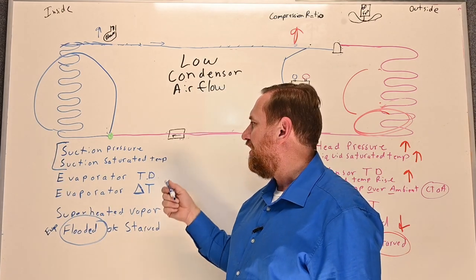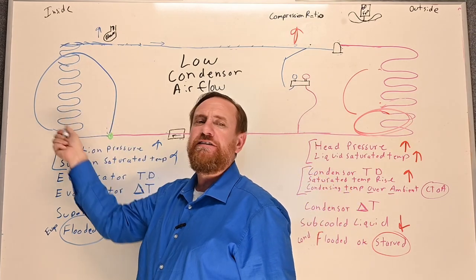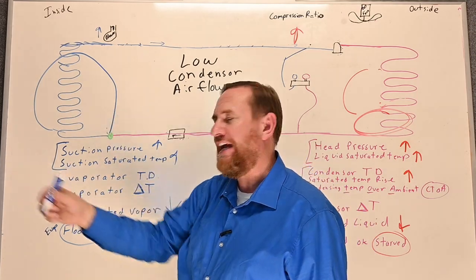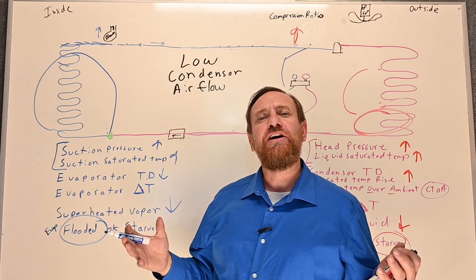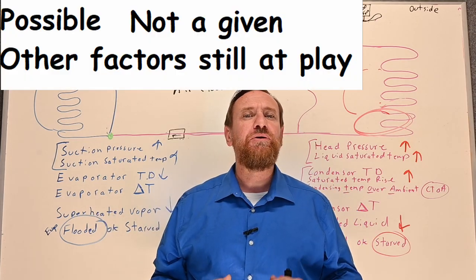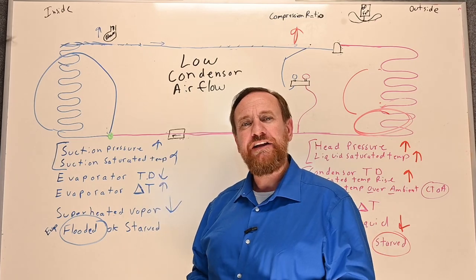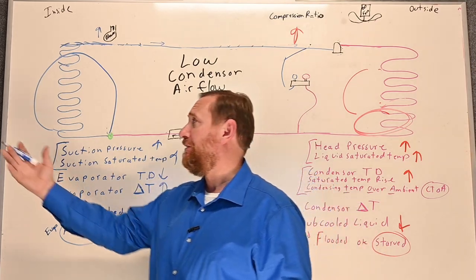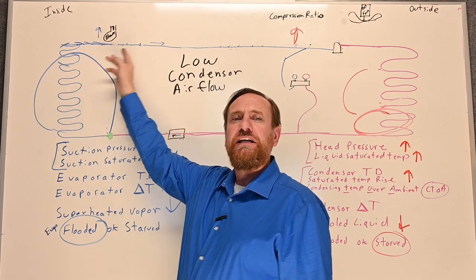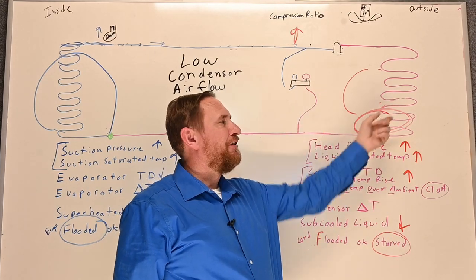That's also going to cause our suction pressure to start going up, and our suction saturated temperature to go up as well. Because the saturated temperature is warmer and closer to the air temperature, our evaporator TD is going to start to drop. However, our evaporator delta T could actually go up because we have more liquid refrigerant in the evaporator coil, potentially absorbing more heat — the temperature difference between incoming and outgoing air becomes greater. On top of that, there's potential for more liquid refrigerant coming back to the compressor, which could damage it.